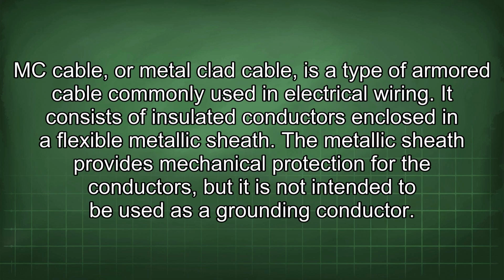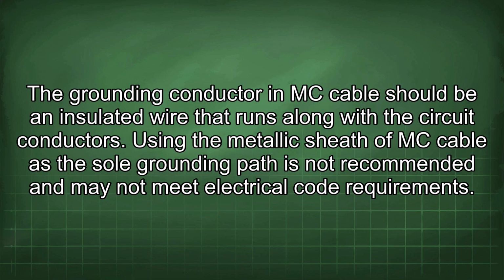MC cable, or metal-clad cable, is a type of armored cable commonly used in electrical wiring. It consists of insulated conductors enclosed in a flexible metallic sheath. The metallic sheath provides mechanical protection for the conductors, but it is not intended to be used as a grounding conductor. The grounding conductor in MC cable should be an insulated wire that runs along with the circuit conductors. Using the metallic sheath of MC cable as the sole grounding path is not recommended and may not meet electrical code requirements.